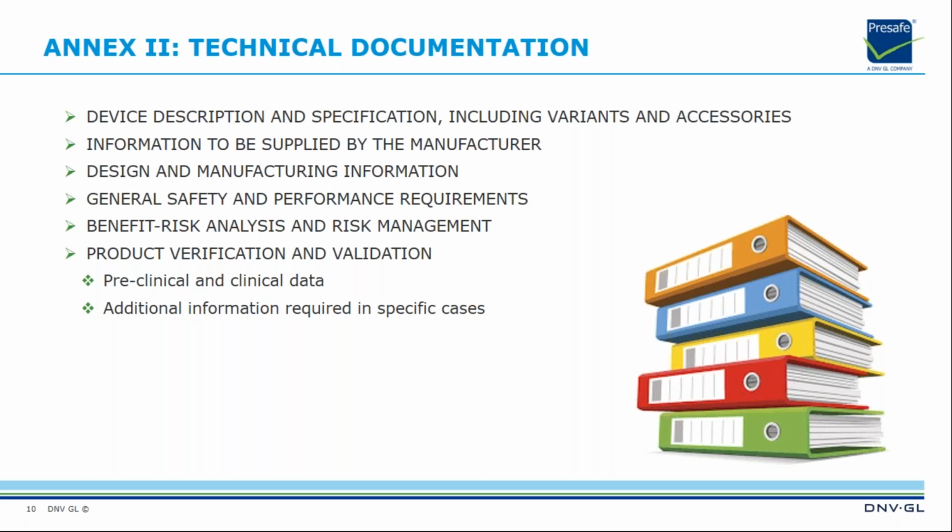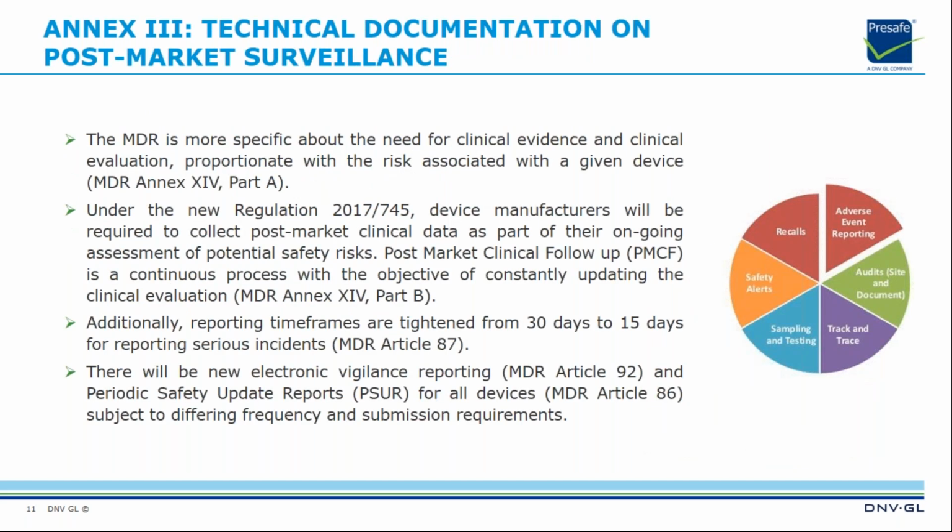This technical documentation must include a device description and specification including variants and accessories, information to be supplied by the manufacturer, design and manufacturing information, general safety and performance requirements, benefit-risk analysis and risk management, product verification and validation, preclinical and clinical data, and additional information required in specific cases. So the manufacturer must provide a technical file including these items.